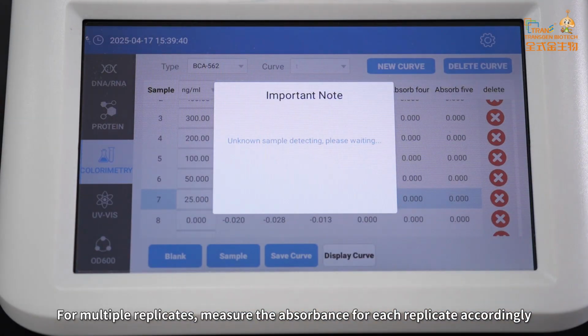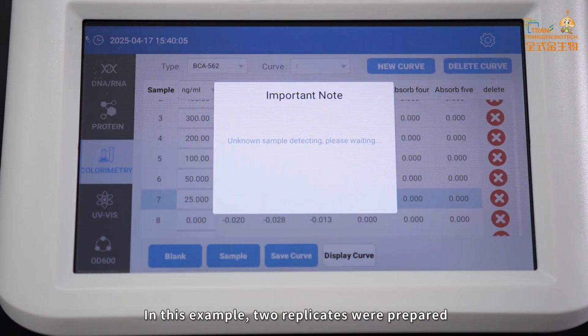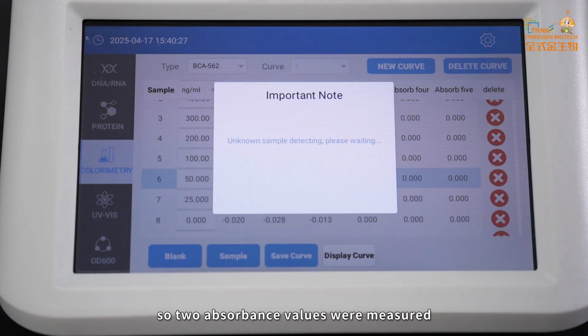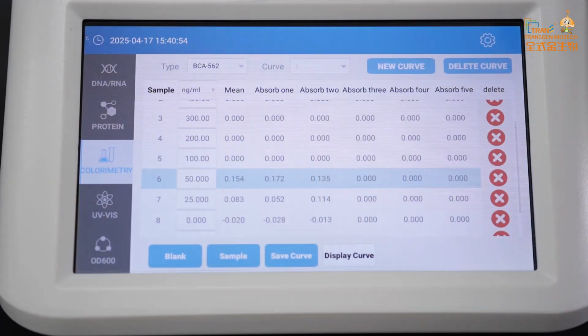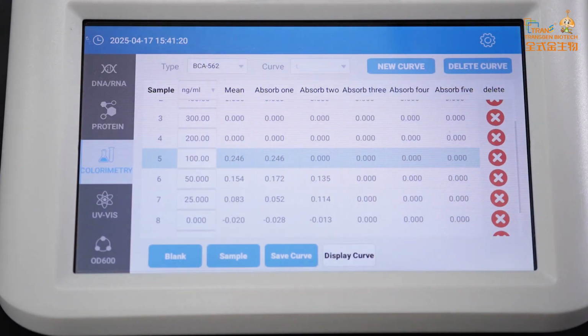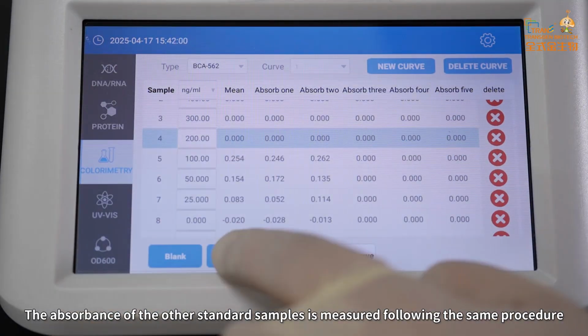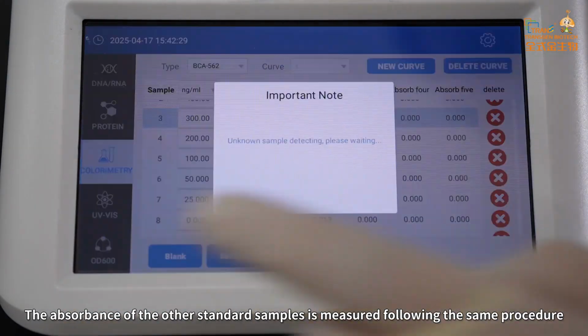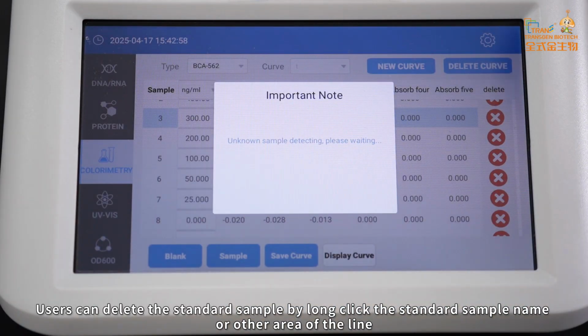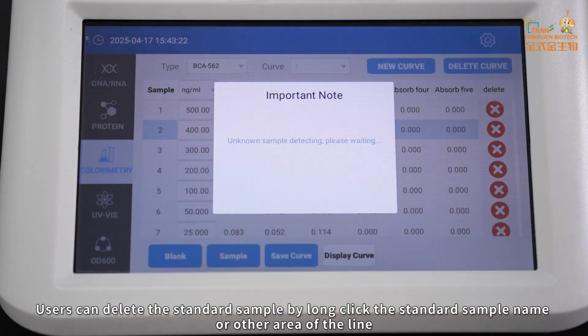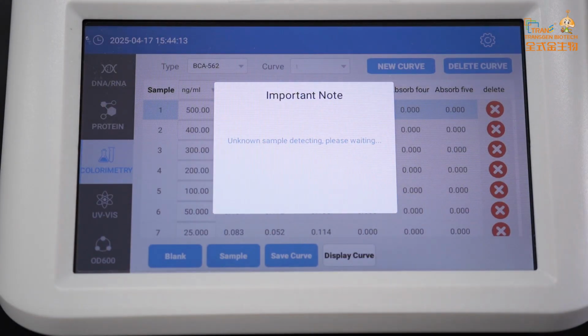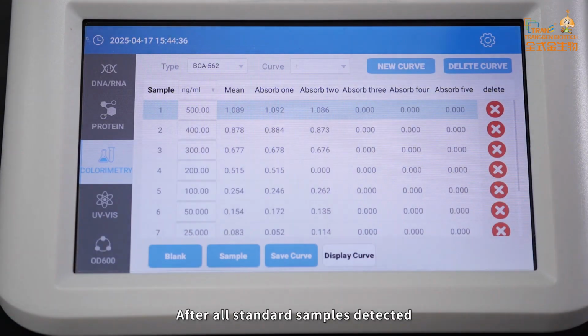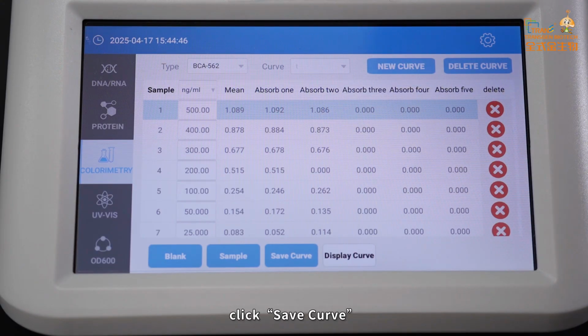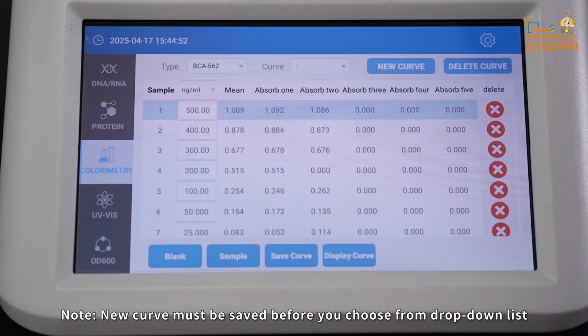For multiple replicates, measure the absorbance for each replicate accordingly. In this example, 2 replicates were prepared, so 2 absorbance values were measured. The absorbance of the other standard sample is measured following the same procedure. Users can delete the standard sample by long-clicking the standard sample name or other area of the line. After all standard samples are detected, click Save Curve. Note: the new curve must be saved before you choose it from the drop-down list.